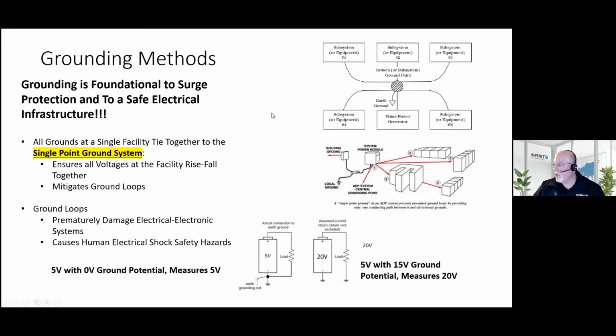So this is all about making sure you have a single point ground system, which is required by National Electric Code. All grounds have to tie together. So if there are multiple ground rods, they have to tie together. If you don't do that, like in this little image here, it's possible that this grounded location might have a difference of potential that's not the same as the one that should be the main one. So what that means is, let's say you're measuring a 120 volt outlet.